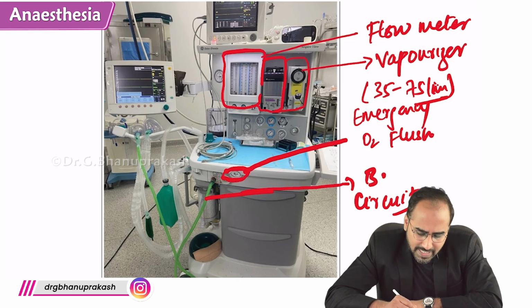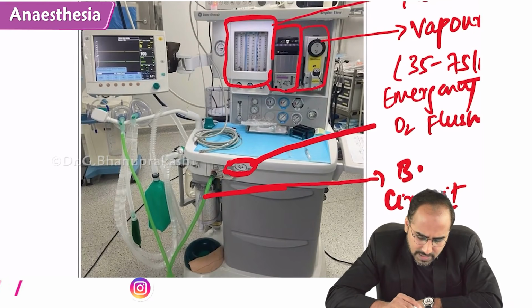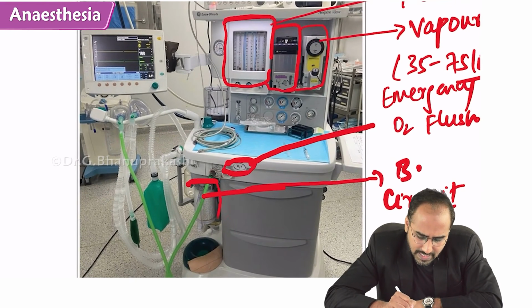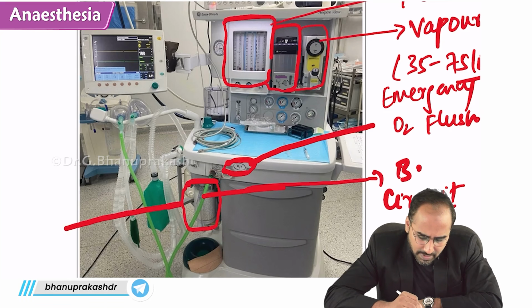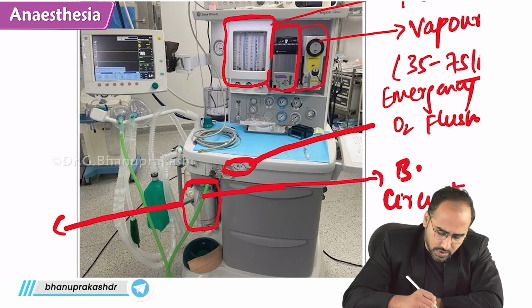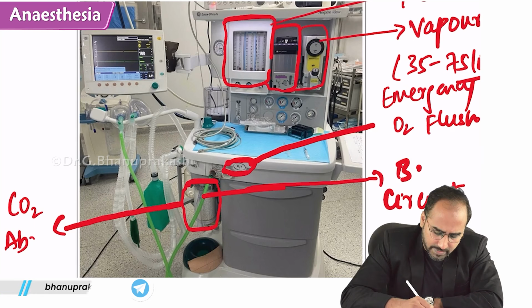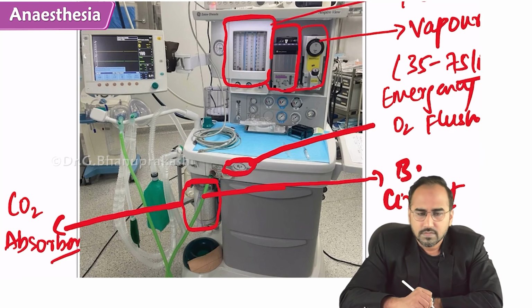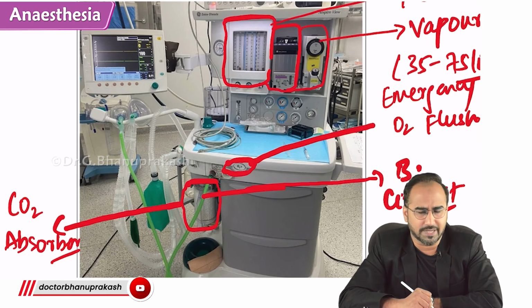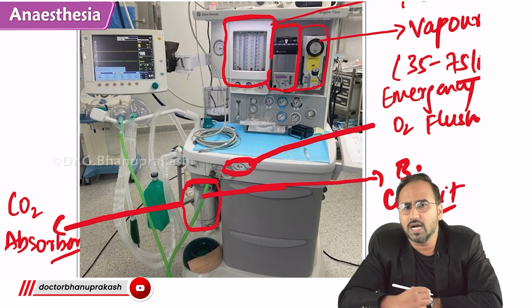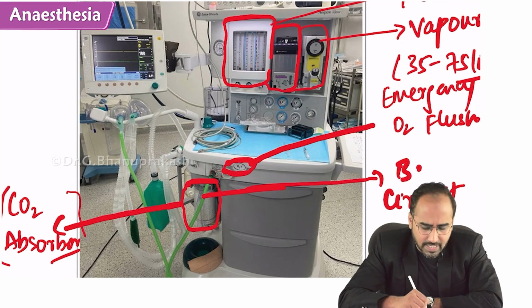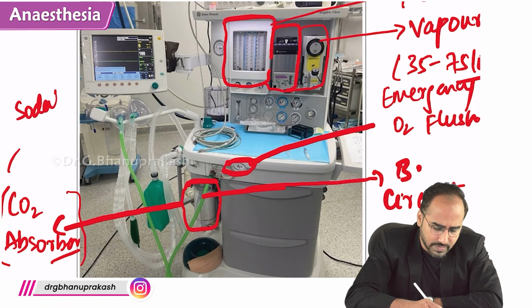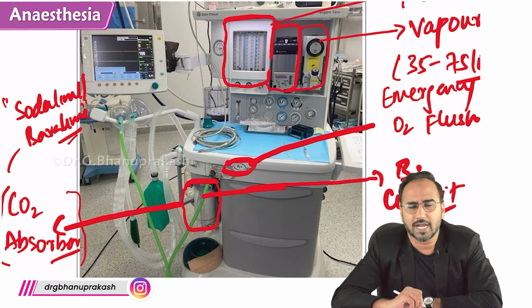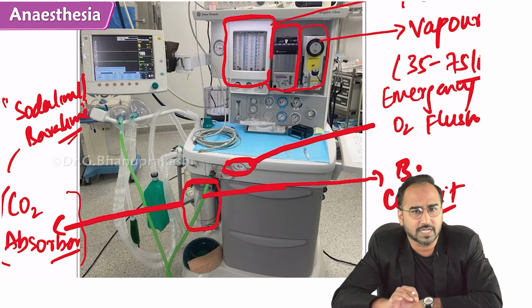Coming to the last part, just beneath the green breathing circuit, if I zoom into the last part of the anesthesia machine, this is the last part, guys. Here is a chamber that absorbs carbon dioxide, called the carbon dioxide absorber or carbon dioxide absorbing chamber. What is the thing in it that absorbs carbon dioxide? It is soda lime or baralime. Soda lime and baralime are the two materials that absorb carbon dioxide.